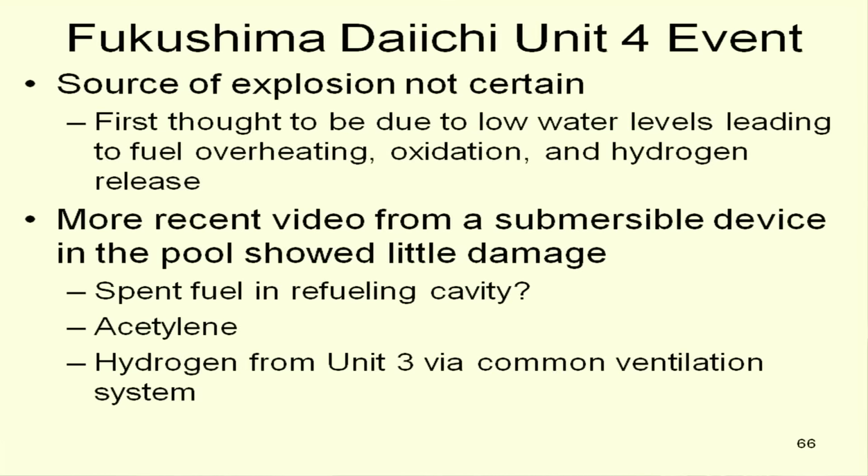remains unknown. They did have both a common spent fuel pool and dry storage on the site, both of which came through essentially unscathed. I certainly would have expected it for dry, and the pool didn't have any problems either. They've had to shore up the Unit 4 pool from beneath a little bit because of some cracking, to provide support.